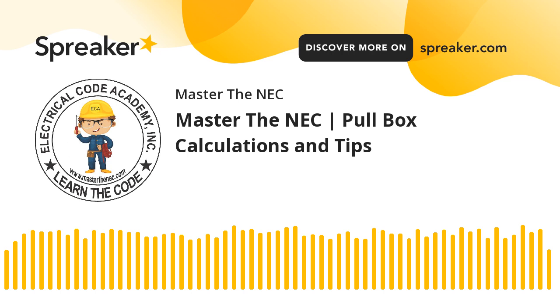You don't solve for Z. Okay? But look at your answers and see. So in the real world, I would tell you, in reality, you're sizing your boxes. You're going to know whether you're coming into the left and going through the bottom, or coming into the left and going out the right, or maybe you're doing larger conductors and you've got raceways in the top, the left, the bottom, and the right, and you've got a big raceway coming into the left and all these other raceways going out. You know which way you're going to route your conductors. You should know this. So you can size your box in the real world based on that.